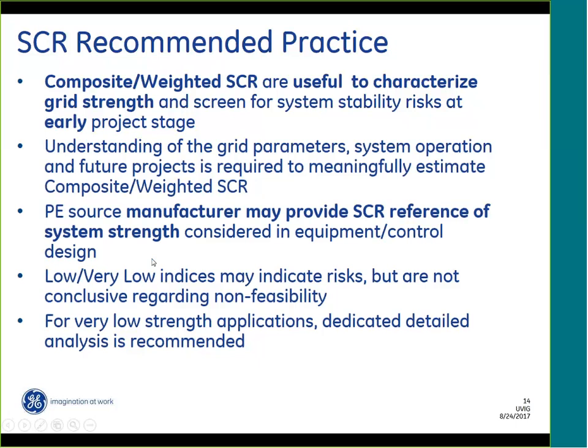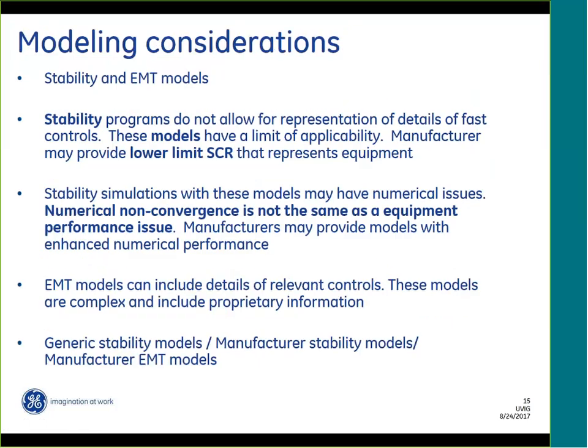So again, you calculate the short circuit ratio, and you probably have a dialogue with the manufacturer to understand how the application compares to the design of the equipment and controls. If, based on that, some risks are identified, the next step is to do more detailed studies than usual. Let's talk about some modeling considerations.